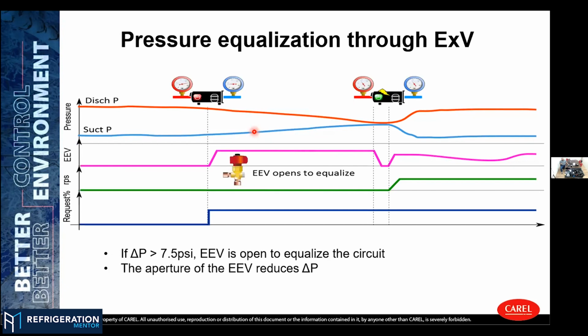Another interesting thing is that in order to make the inrush current of the compressor lower, what we can do is equalize the pressure inside the system before starting up the compressor. So basically, we open the electronic expansion valve. That is generally a feature that comes with the variable speed compressor with the BLDC. And we can simply reduce the pressure differential just for the startup procedure. So we make sure that the compressor can start running with a lower current, and this can save a lot of the motor coil inside the compressor. So we do not force the compressor with a higher current to start up. We can just make this startup phase very smooth.